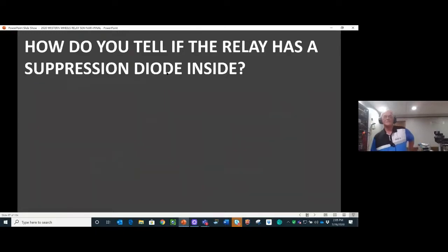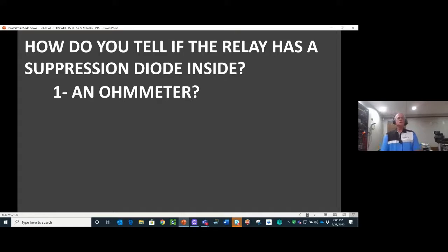How do you tell if a relay has a suppression diode inside or not? If I was to throw that open to the audience, how would I get an answer? You've got a relay, you don't have a schematic, you don't have a wiring diagram, and you want to know if it has a diode inside or not. Well, one answer is you could pry the top off of it, I guess, and look for a resistor or a diode. How about this one? Could you use an ohm meter to tell? You know that if a diode is hooked up to an ohm meter and you reverse the leads of the ohm meter, the diode will give you two different resistance readings. Would that work in a relay?